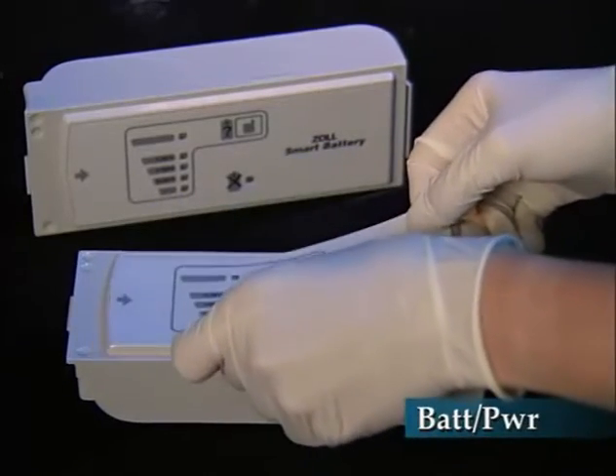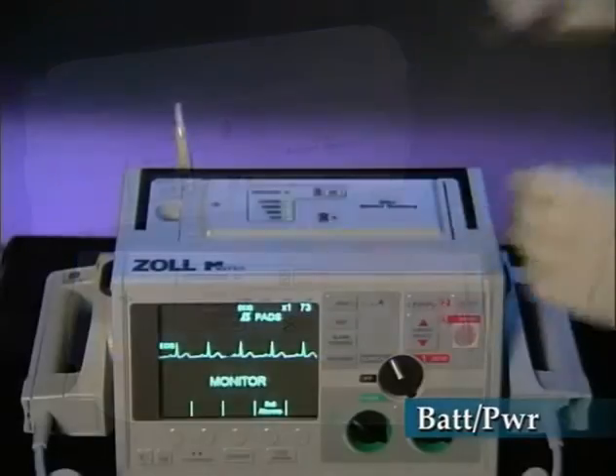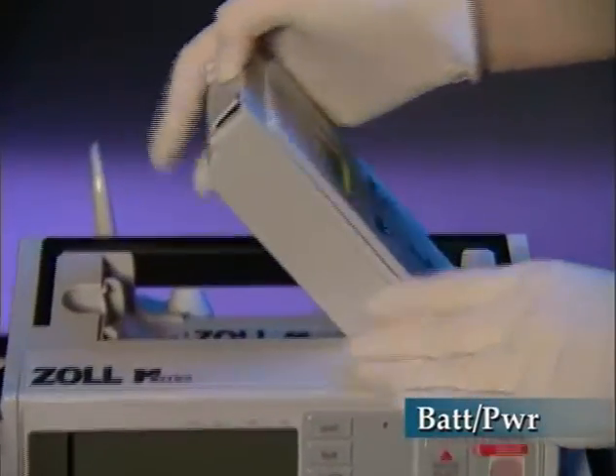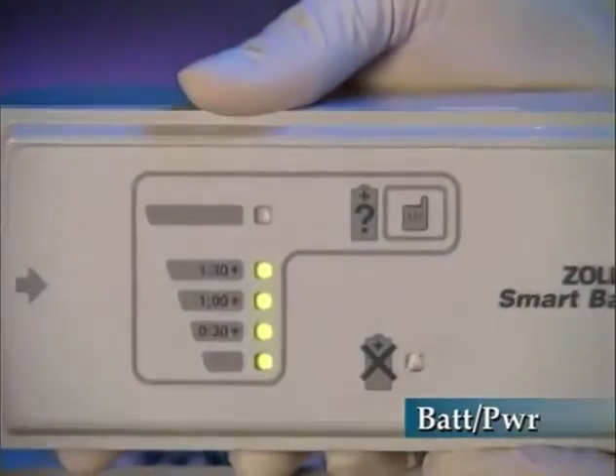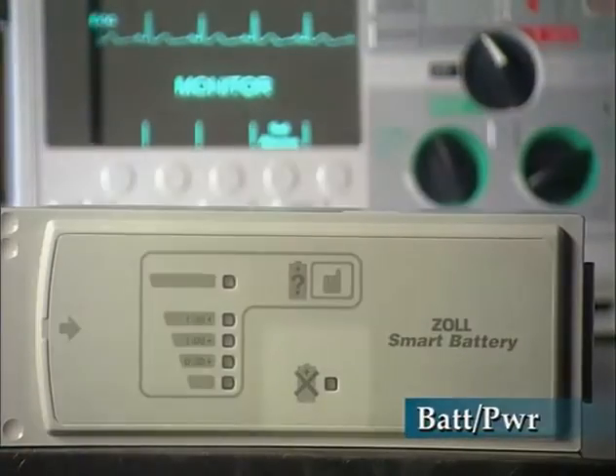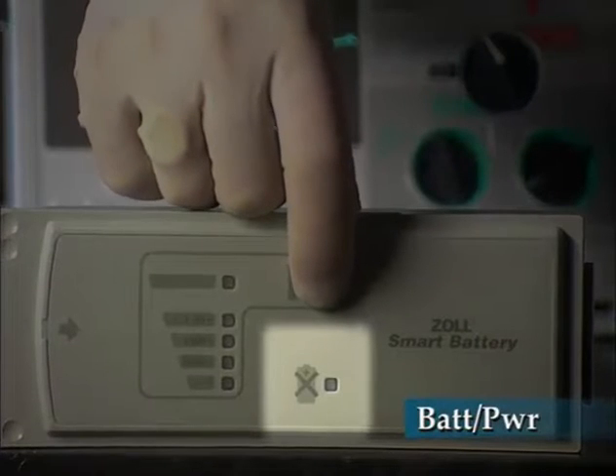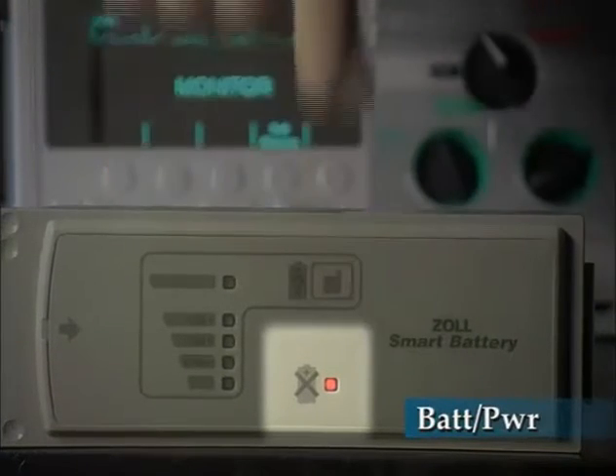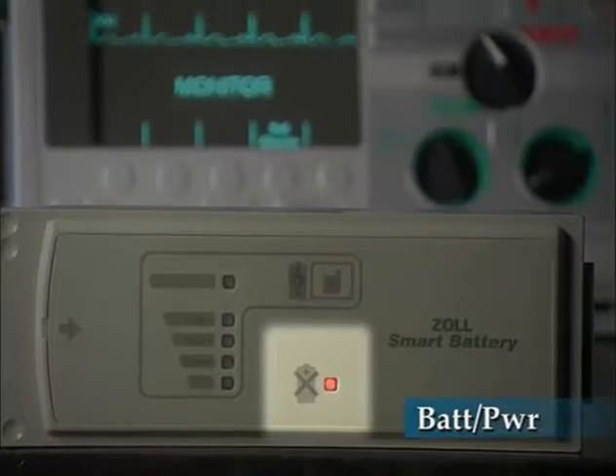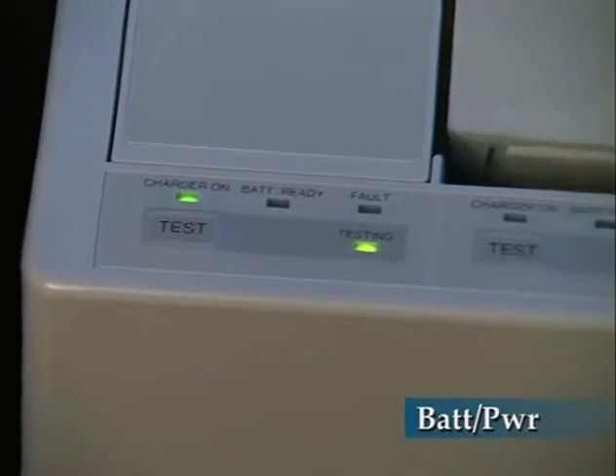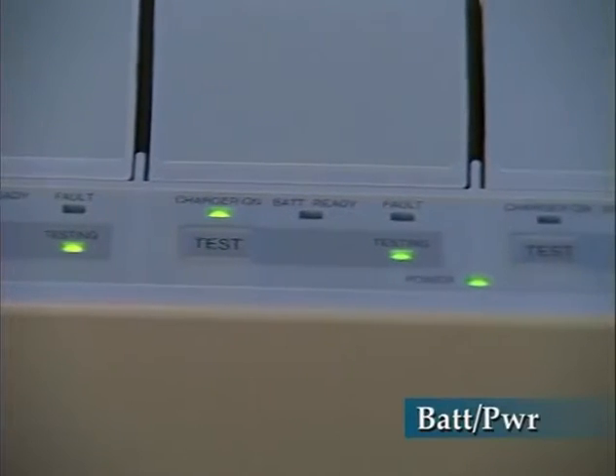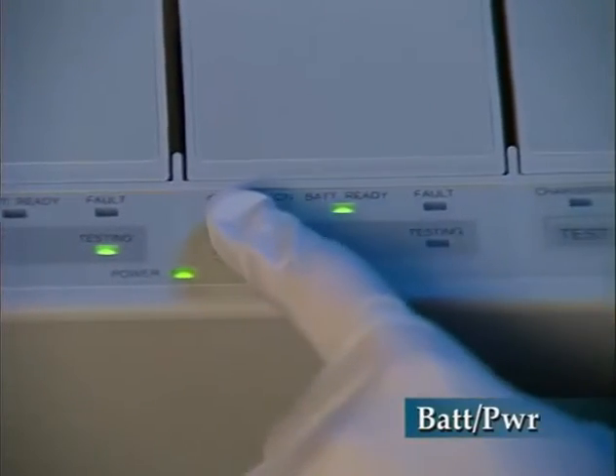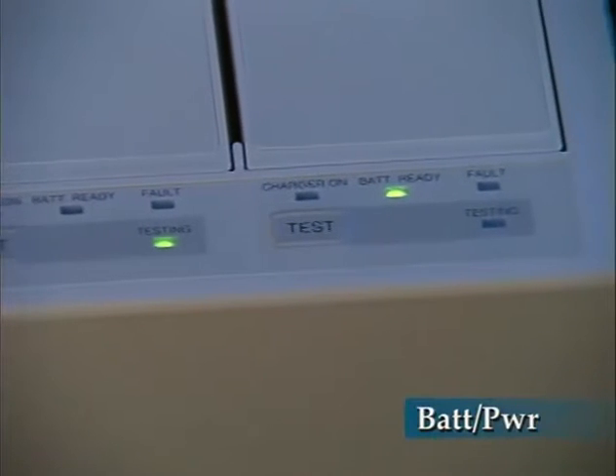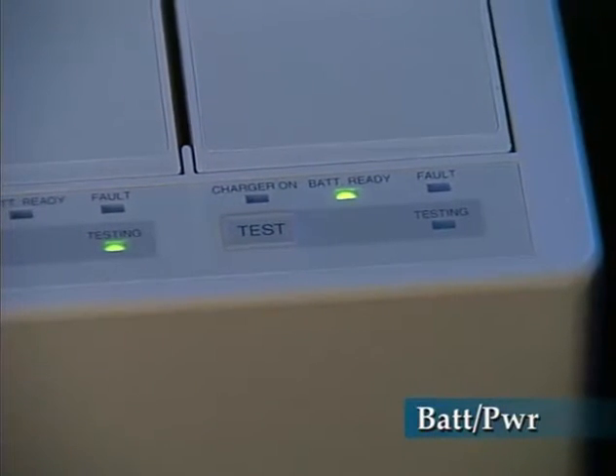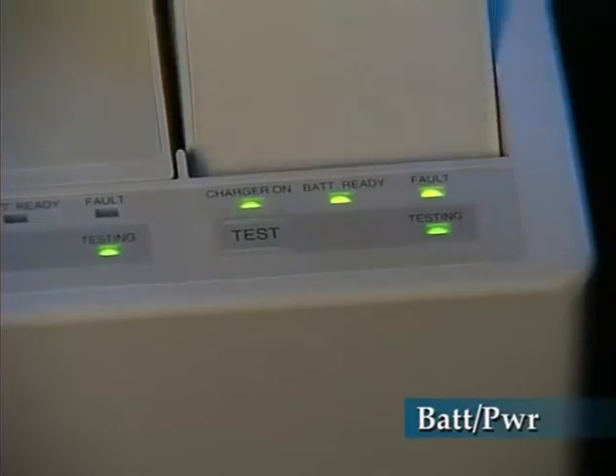Smart battery capability may be added to all ZOLL Smart Ready battery packs. A smart battery displays remaining operating time when in use. Smart batteries have a do not use indicator that will illuminate if a smart battery has not been recalibrated after 20 discharge and charge cycles have occurred, or if another fault exists. Batteries require periodic testing. The ZOLL 4x4 with auto test capability provides for 100% automated testing with each recharge cycle. Batteries that test ready provide a minimum of 1.5 hours monitoring time.